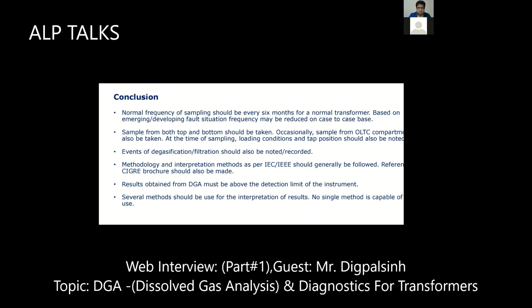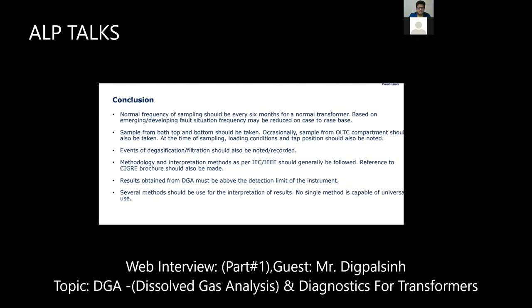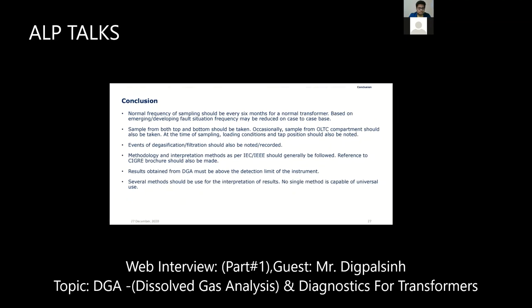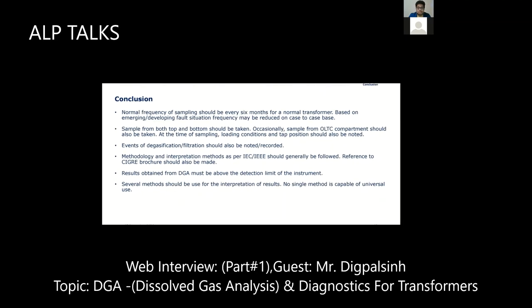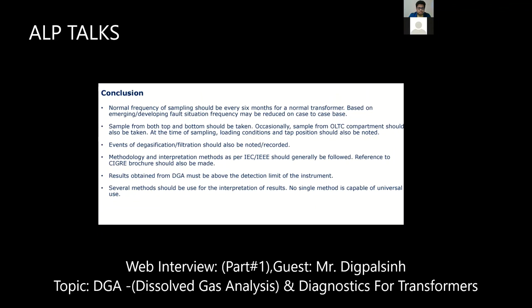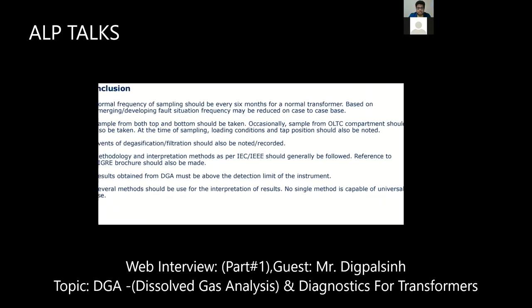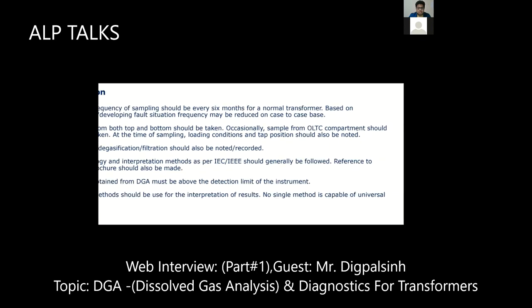If you do it in IEC and say there is a low energy fault, that is actually not the right practice. You have to cross-check with a number of methods, 3 to 4 methods, or at least 2 to 3 methods. That gives a good understanding. Several methods should be used to interpret a result. No single method is universal.